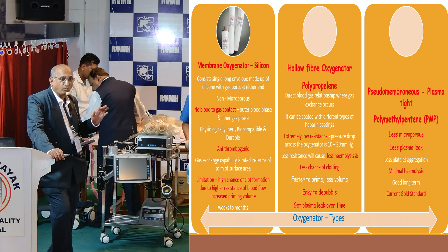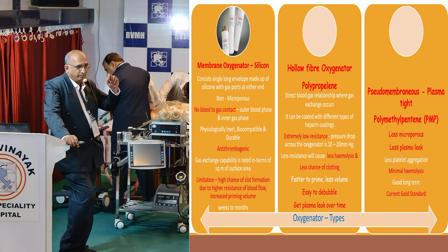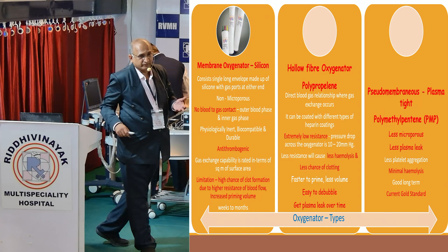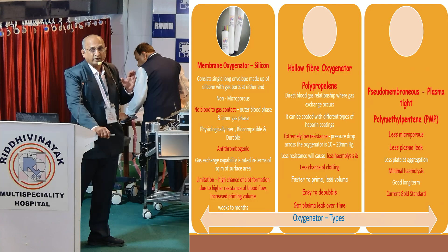Then you have a hollow fiber oxygenator which you use usually in case of bypass surgery. That is known as the polypropylene oxygenator. Okay, that is a hollow fiber, so there are pores. The problem with this oxygenator is that after 4 to 6 hours it develops plasma leak. So that cannot be used for ECMO, because in ECMO you require longer.